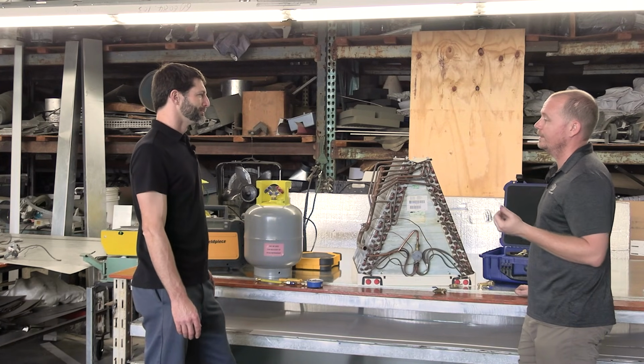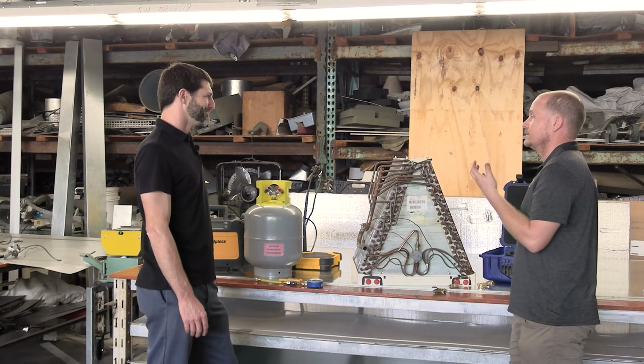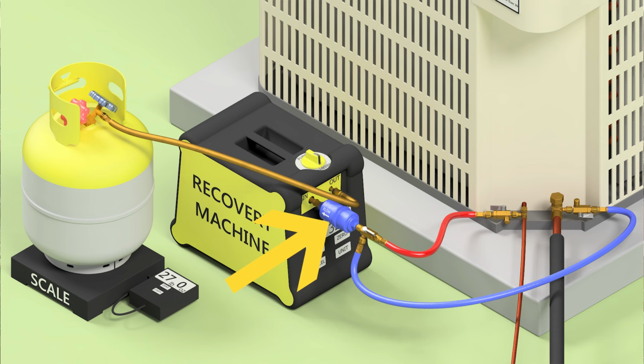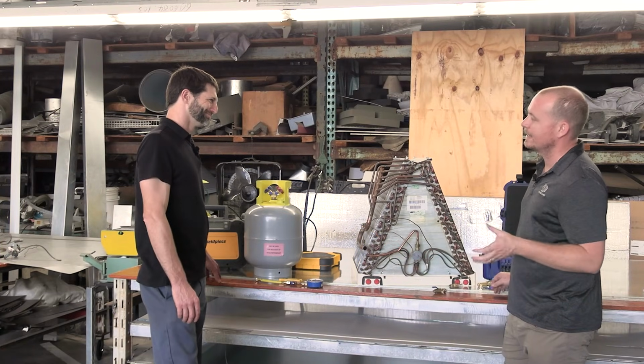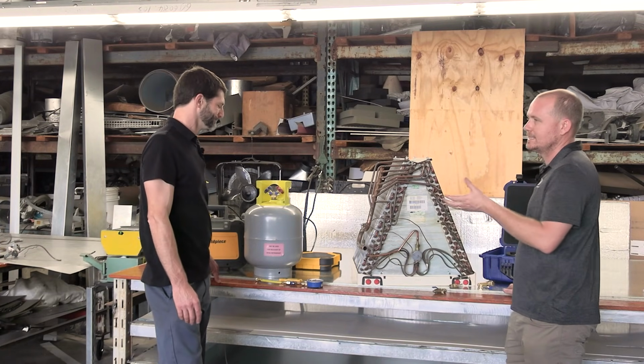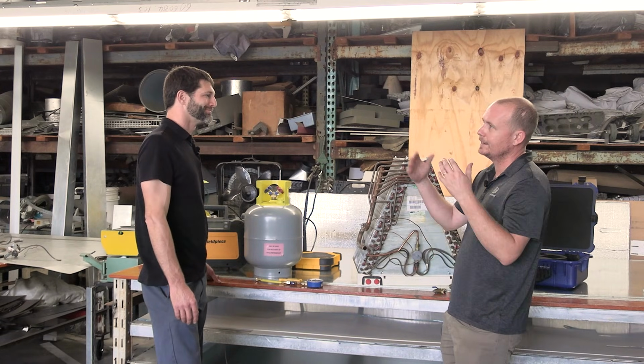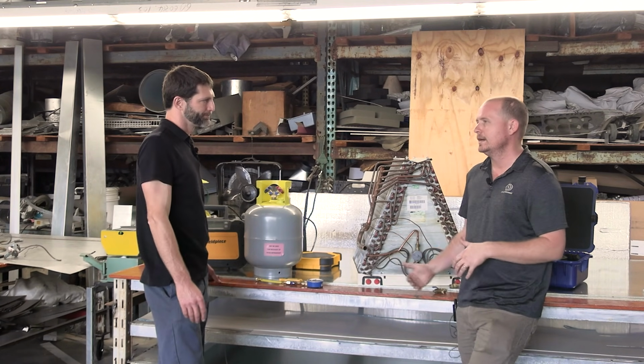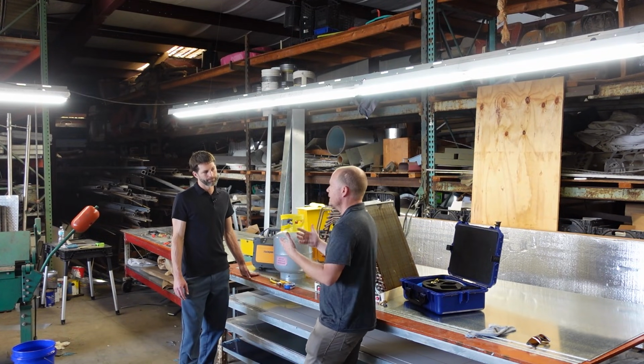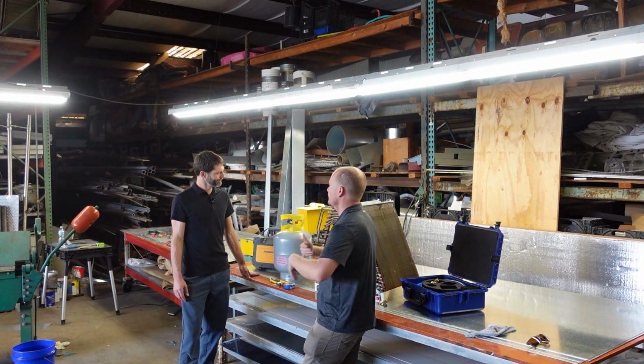Some people will point out that it is a good idea to put an inline filter dryer in place on your recovery machine. The point of that is really to protect your machine, because you're not going to clean dirty refrigerant in one pass. The filter dryer in a system can dry and clean that refrigerant because it's gotten multiple passes.